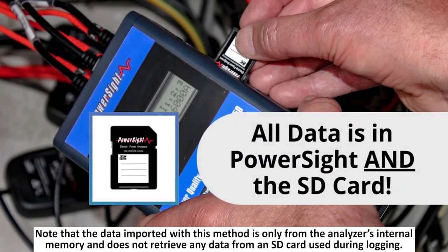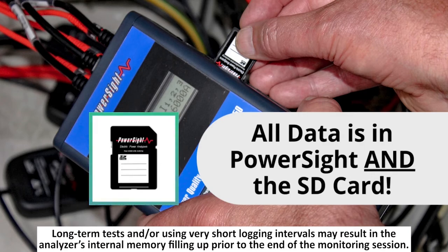Note that the data imported with this method is only from the analyzer's internal memory and does not retrieve any data from an SD card used during logging. Long-term tests and/or using very short logging intervals may result in the analyzer's internal memory filling up prior to the end of the monitoring session.